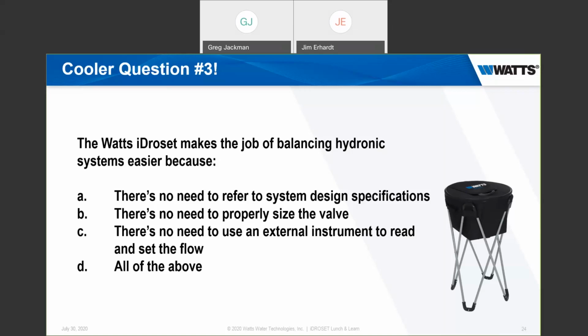Yeah, well, see, I kind of set them up for that, right? So, there's no need to refer to system design specifications. That's not true. We need to know what the required flow rate is for each heat emitter for each balancing valve so that we select the correct balancing valve. Balancing valves are selected not on their line size, in other words, their tapping size. They are selected by the flow rate that they must handle. So you select a valve based on that. There's no need to properly size the valve. Well, that goes into what I just described. No, the valve must be sized correctly based on the flow rate. So you select the valve based on the flow rate window that it covers in comparison to the actual design flow rate.